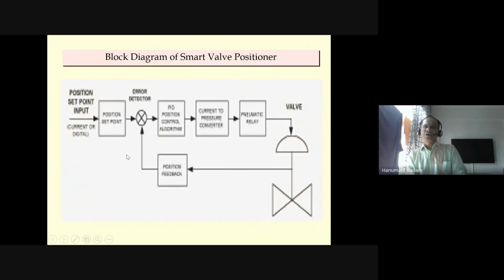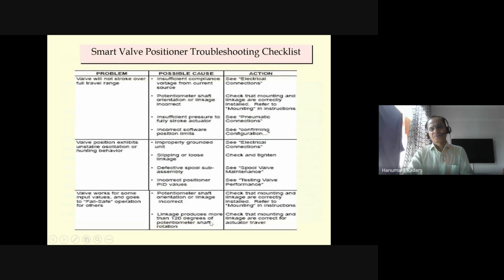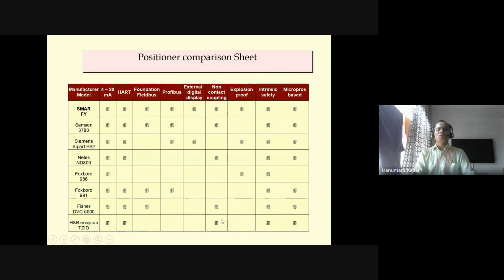So if you see any smart valve positioner, this is your controller, and this you can see here we have discussed. This is the link, position feedback, and you can see the set point, current or pneumatic input is coming from the control room or I2P, right? And you can see the block diagram here where you can have PID also, other pneumatic circuitries are also there. I2P is also inbuilt, error indicators. So first we'll see the valve positioners. Normally in the valve positioners of any manufacturer, you can see these are the manufacturers.